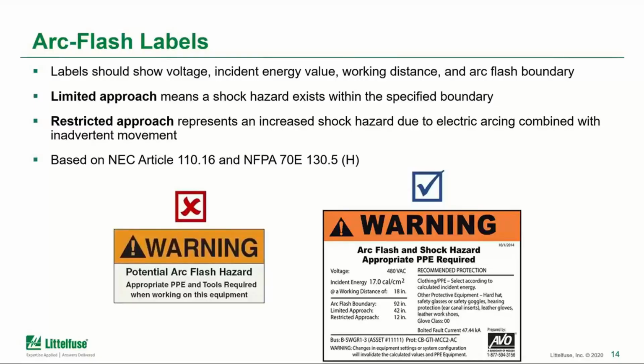And again, a couple of important items there are the limited approach boundary and the restricted approach boundary. The limited approach identifies that a shock hazard exists within that boundary and that non-qualified people should really stay back unless they have the appropriate PPE or are escorted by somebody. And the restricted approach is a higher level of risk where only qualified workers with training, with a work plan, potentially even an energized work permit, will enter that space to do the work.